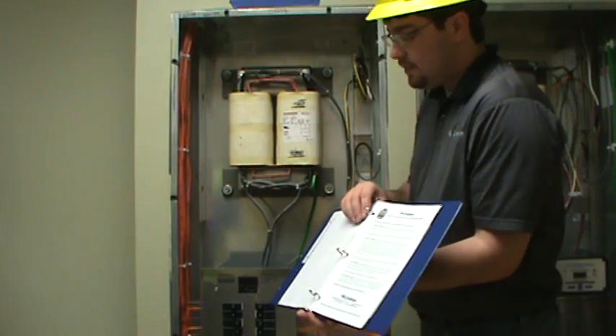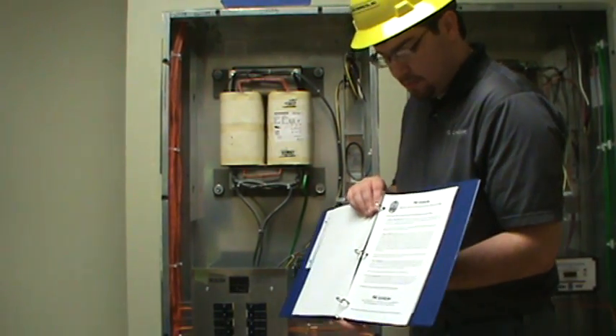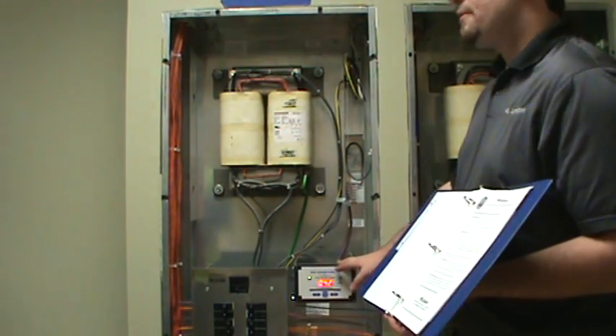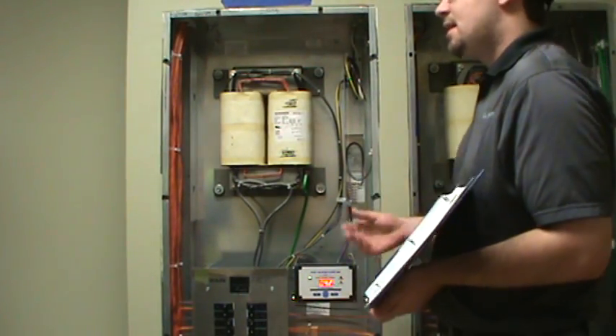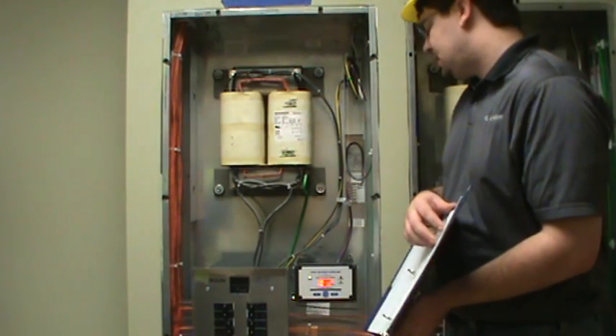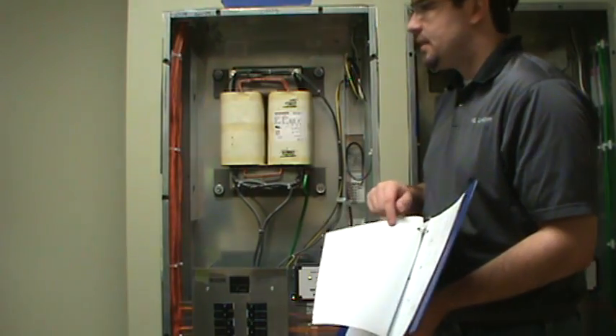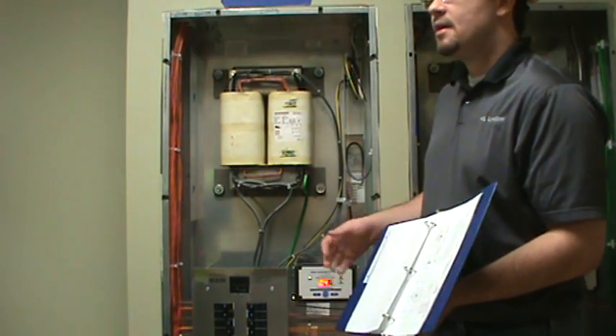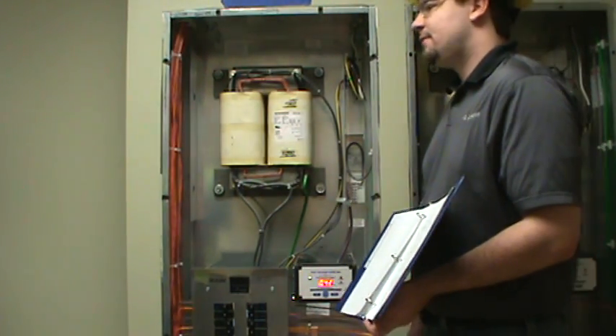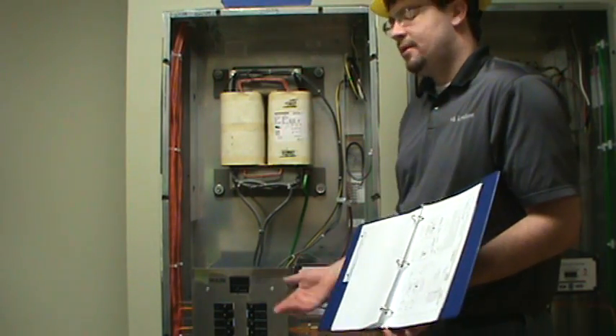We have some basic definitions here. Normal mode, alarm mode, test mode. I don't know if you noticed, after we do that self-test, it actually goes through that calibration process automatically. It takes about 45 seconds or so, and then it'll come back up with a reading just like that. The system won't see it any differently. It won't stop any power.